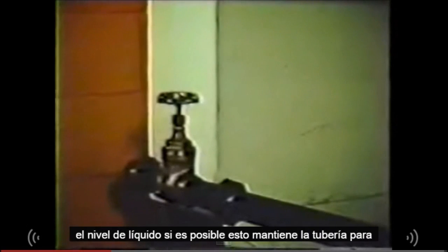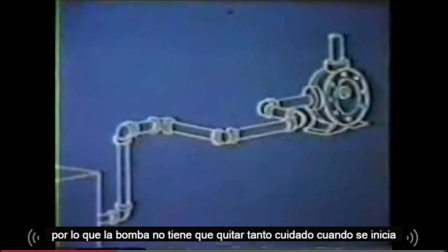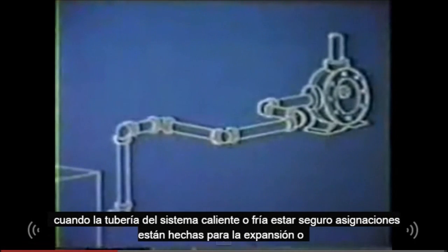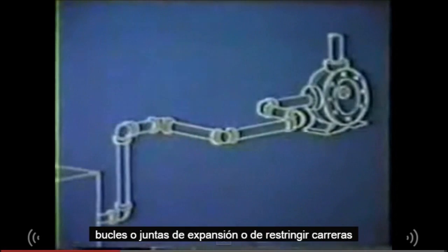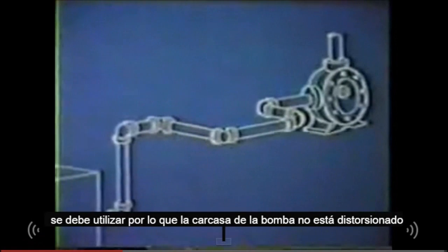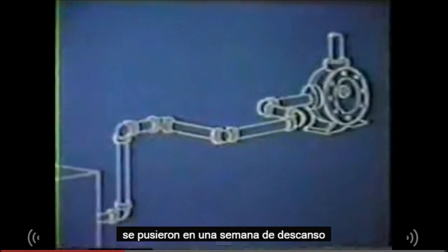For a suction line with a long horizontal run, keep the horizontal portion below the liquid level if possible. This keeps the pipe full so the pump does not have to remove so much air when starting. When piping a hot or cold system, be sure allowances are made for expansion or contraction. Loops or expansion joints or unrestrained runs should be used so the pump casing is not distorted or put into a bind.